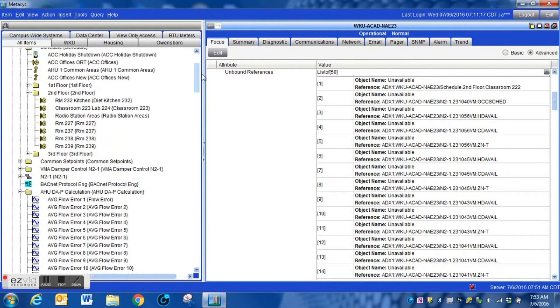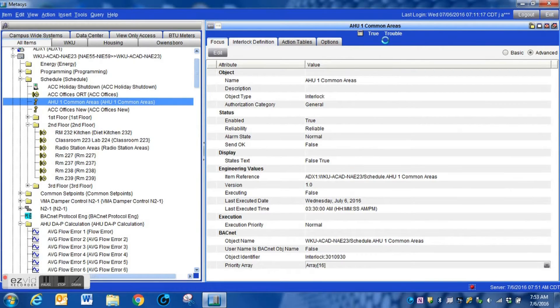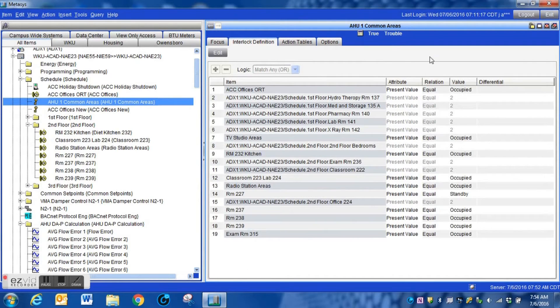If you look at your interlocks, sometimes they will flag that they're in trouble if a reference is missing — and sometimes they may not, depending on whether it is on the input or output side of the interlock. If you simply click on the reference, you can see that several of these items are grayed out because they are no longer within the system due to the renovation. We need to go through here and delete all of these points that no longer exist.